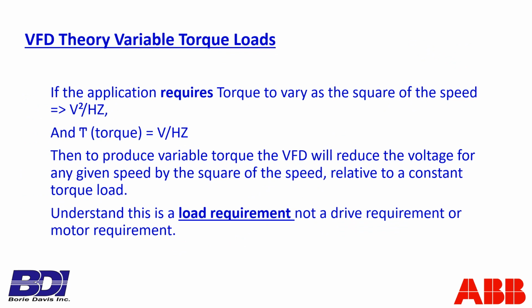All right, so if the application requires torque to vary as the square of the speed, then you set the voltage to volts squared per hertz. This is a parameter in the drive, and it comes from the factory that way because that's our load requirement. Okay, and since torque is equal to volts per hertz, then we just do volts squared per hertz. Okay, so it will produce the square load function of the voltage for the load requirement.